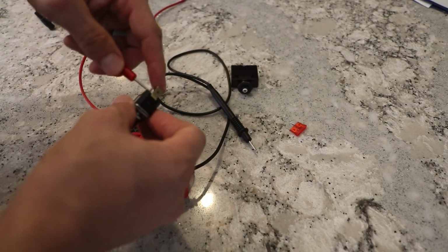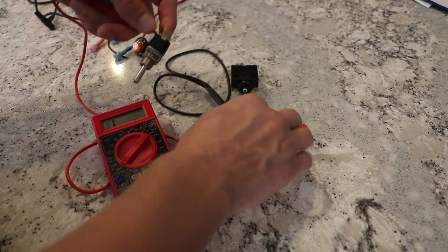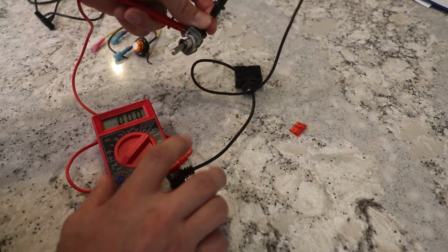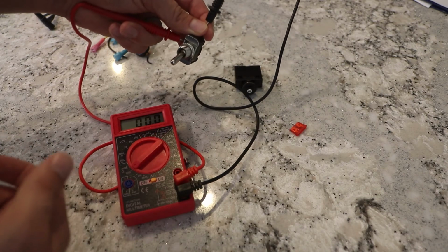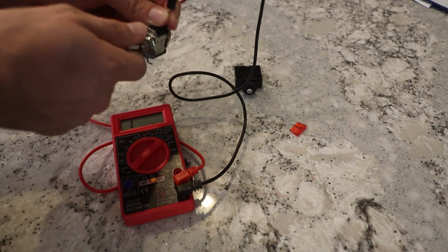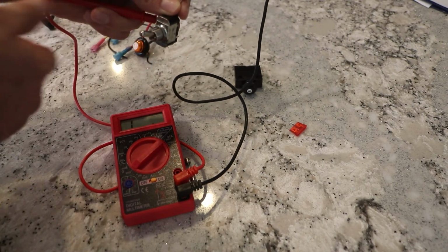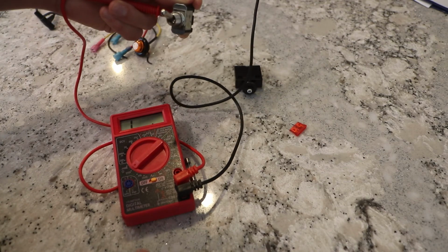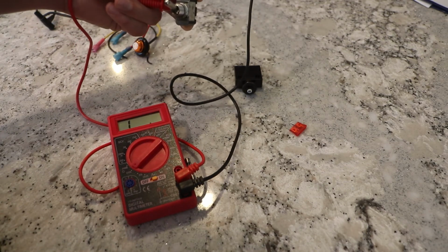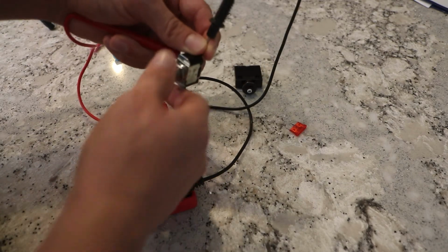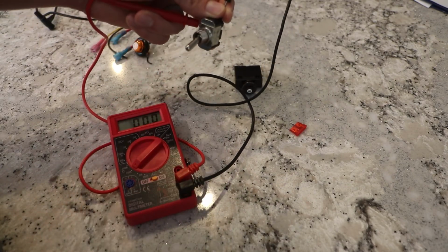With a switch, you want to verify two things. We verified at this point that we have no resistance at all when the switch is on, and when we flip the switch off, we've got infinite resistance. So anytime you test a switch, make sure both of those work, so you're not leaving stuff on and draining the battery unknowingly, but also make sure it works the other way.